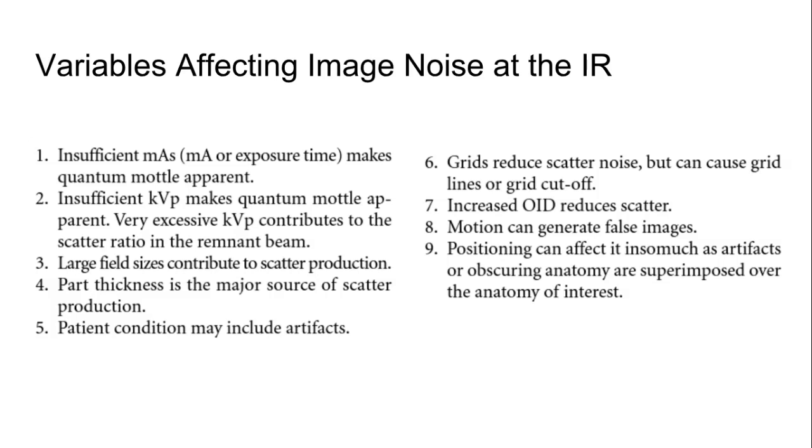Grids, we said, will reduce scatter. But there is a potential, if you use the grid incorrectly, that you can also get noise. If the alignment or the SID range is not correct when you're utilizing a grid, you can get noise. If you don't increase your exposure enough to compensate for the grid ratio, then again, you can get a quantum mottle, right? You just wouldn't have enough data again.